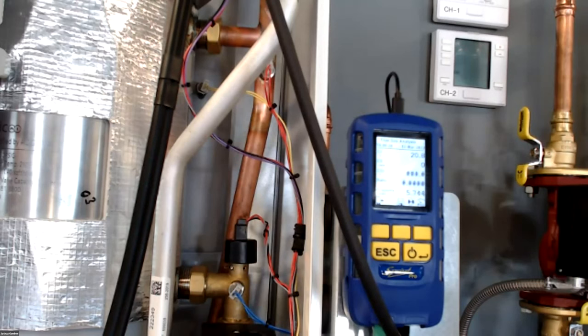The Venturi has larger orifices, so the thing runs a little richer, essentially, and it's pretty much taking care of that problem. But if you have a howling boiler, if you come across it and your specs are all in, your gas pressure is good, your venting's good, everything's crossed off, give us a call. We can walk through increasing our ignition fan speed, and also playing around with the elevation usually takes care of it. But the foam, we've got to make sure that's in there.